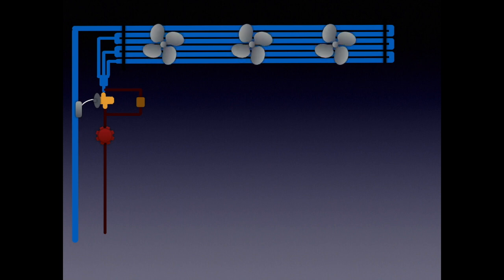Before we navigate back there you'll see a little additional piping basically jumping around that TXV or that metering device. And that is an inline check valve to allow for reverse flow during our defrost cycle. We'll go over that a little bit here later.